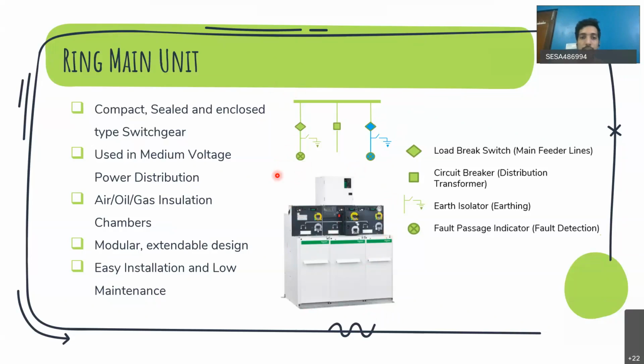This example I have shown is for a 3-way RMU: one incoming, another outgoing, and the third one going to your distribution transformer. This is denoted by a load break switch where your main feeder line is connected, another load break switch where the outgoing feeder line is connected, and this is a circuit breaker where your distribution transformer is connected. Earthing facility is also provided to the load break switch limbs.